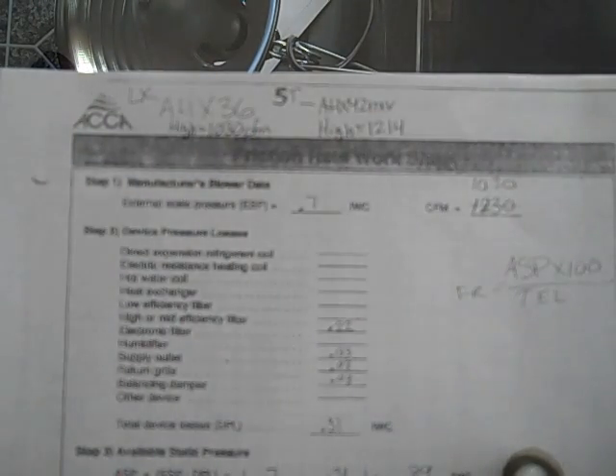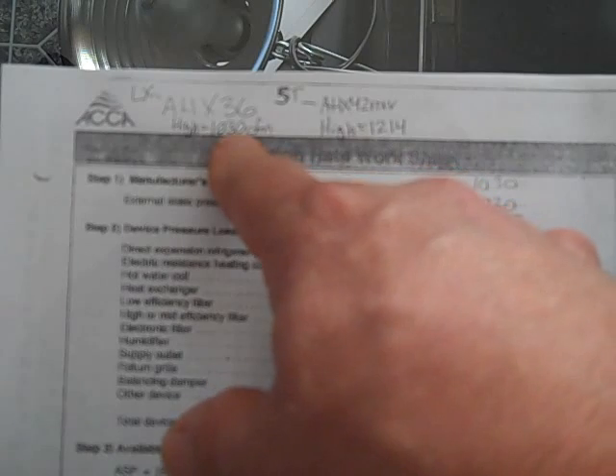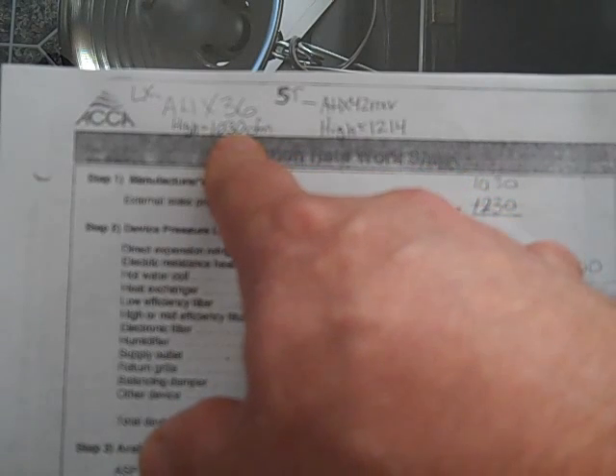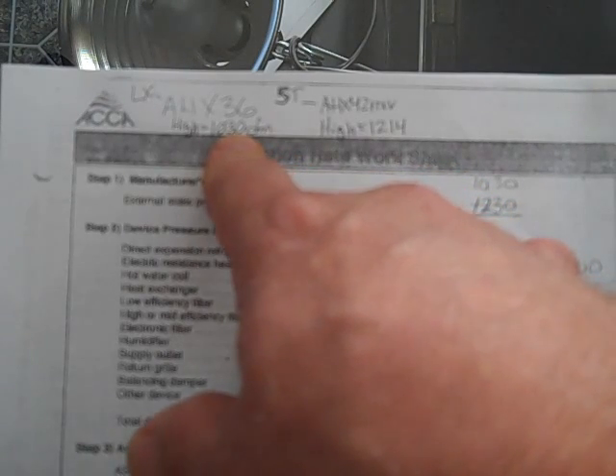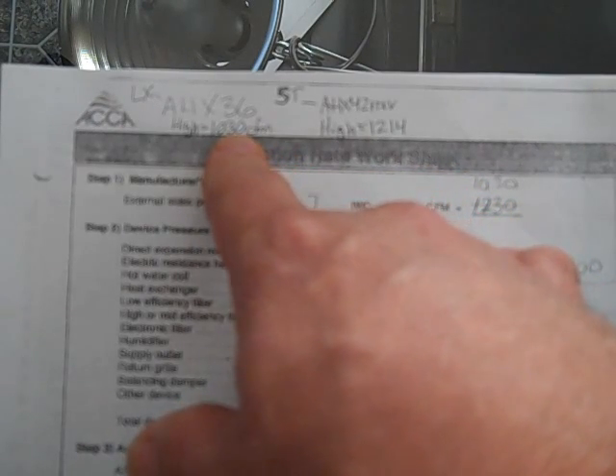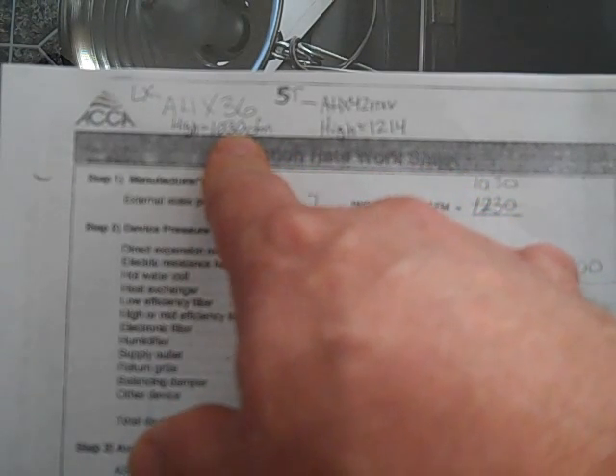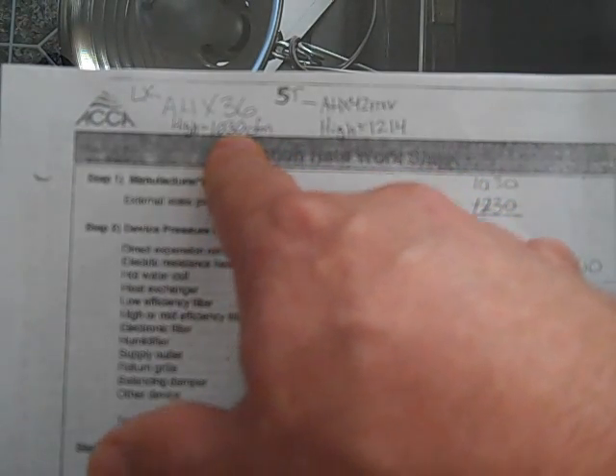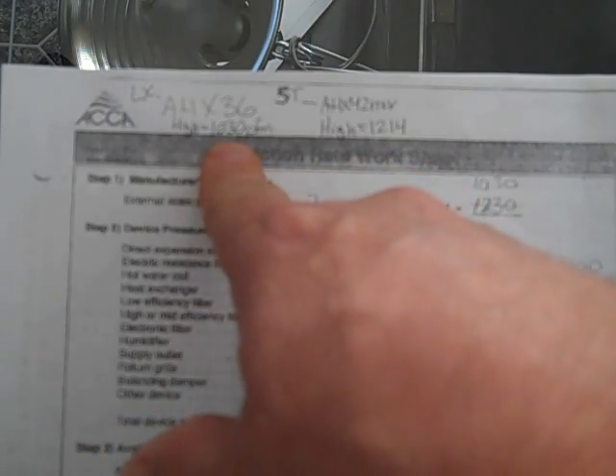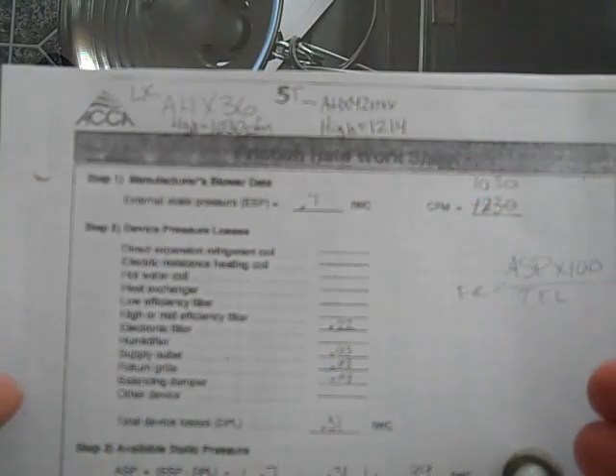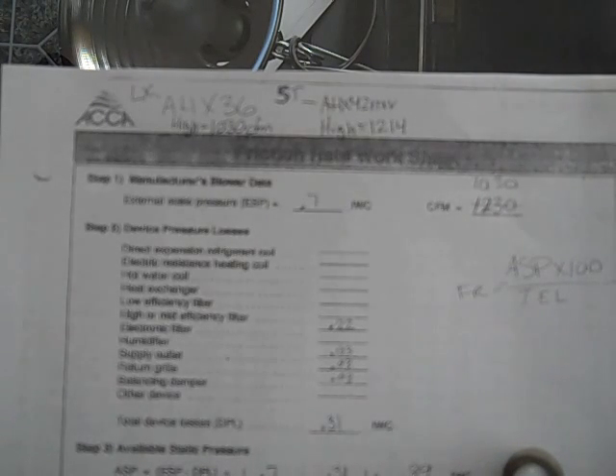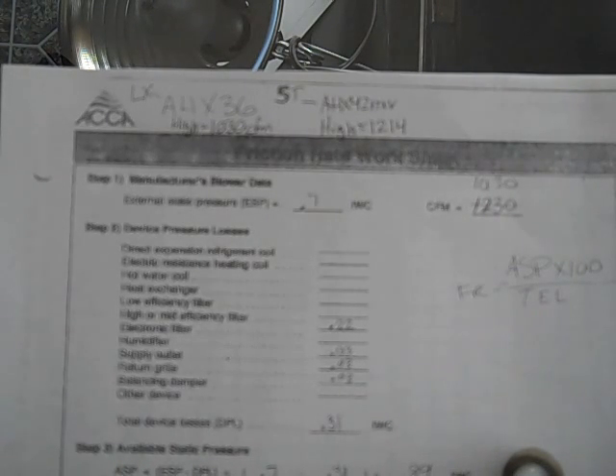So I looked up the nominal airflow. Actually this value comes out from how I calculated the available static pressure and the external static pressure. Air Handler's going to be a little simpler. There's less components to deal with. But I've kind of just started off on this sheet. And I arrived at 0.7 of external static pressure. That's really what it's going to run at.